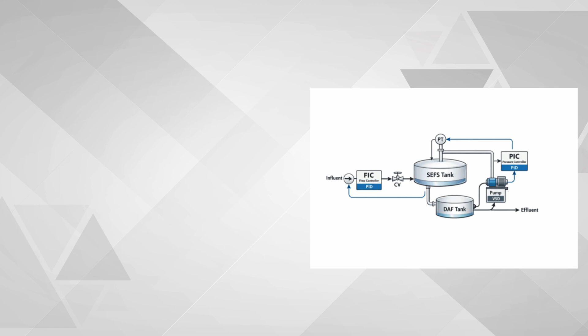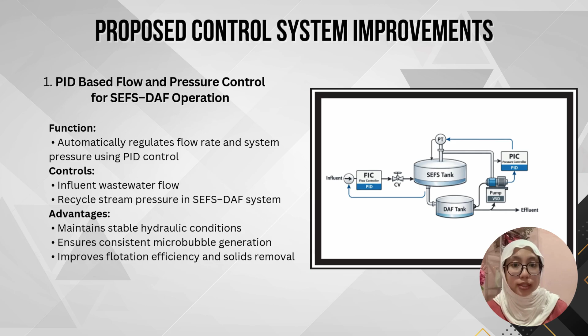Okay, for the first improvement, we implement PID control for flow rate and system pressure. This control system will automatically regulate the influent flow and recycle pressure in the SEFS DAF unit by maintaining stable hydraulic conditions. So the system will ensure constant shear mixing and microbubble generation. As a result, bubble particle attachment becomes more effective and flotation performance is significantly improved even when the wastewater flow fluctuates.